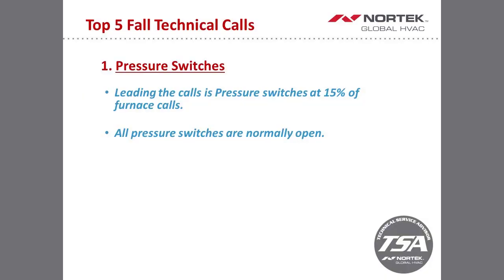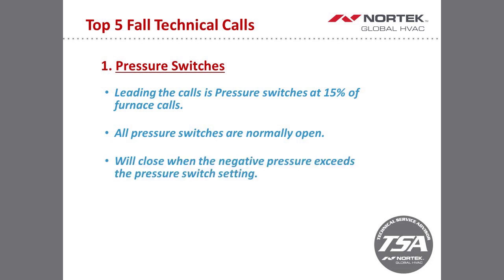If we get a call on a pressure switch closed fault, normally it's the tech prematurely jumping the switch out, which will throw that fault code on the board. So from a troubleshooting standpoint, if you want to jump out a pressure switch, just wait one second, let the inducer kick on, then jump the switch, and you'll be good to go. The number on the pressure switch, which we'll look at in a second, is the number upon pressure fall. That's not the number of the vacuum reading it takes to close the switch. Generally speaking, just add 20% to that number and you'll be good to go. If you're pulling 20% more than what the switch is rated for throughout a heating cycle, you'll be just fine. But just remember, all the pressure switches are normally open.